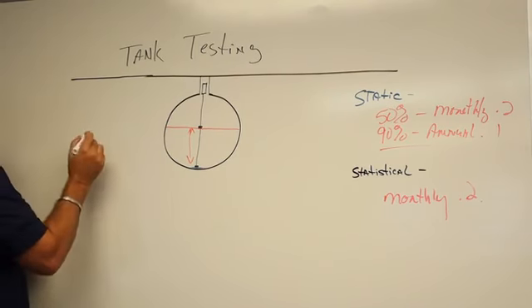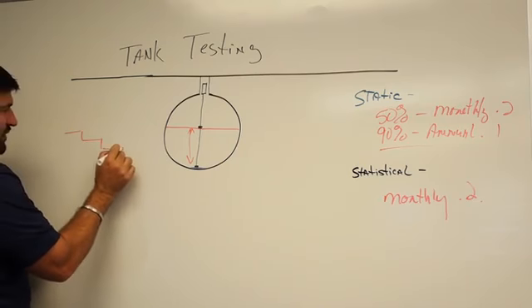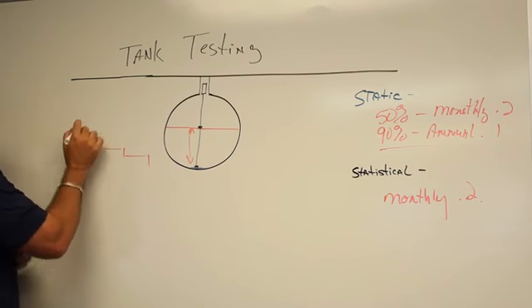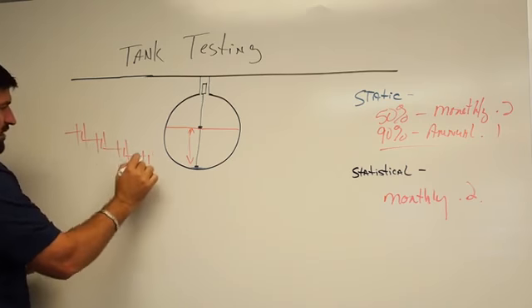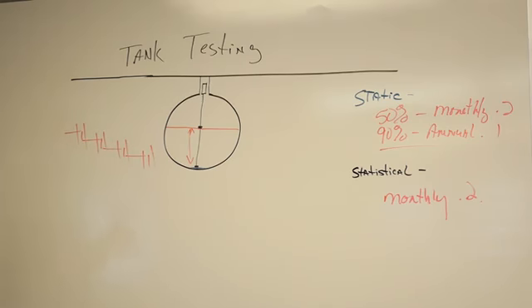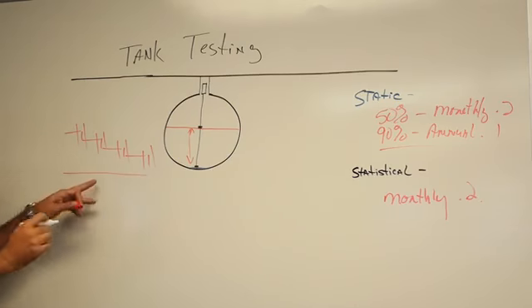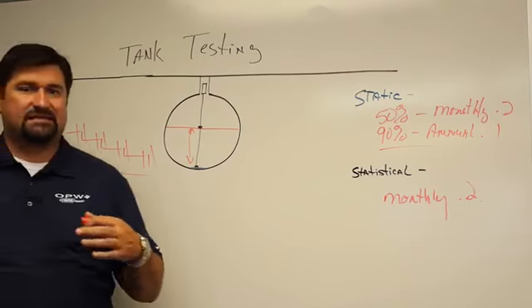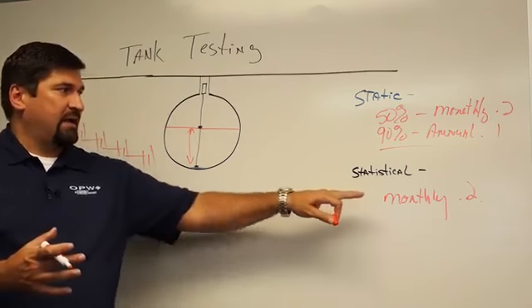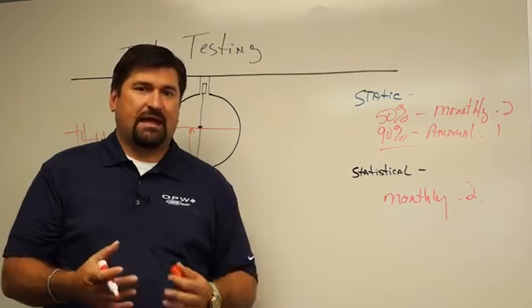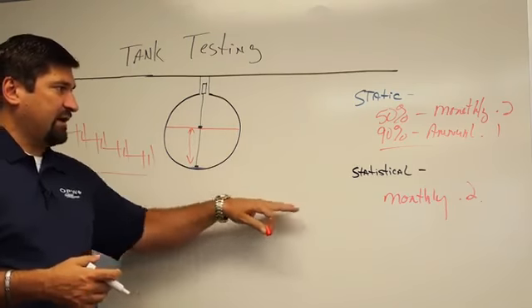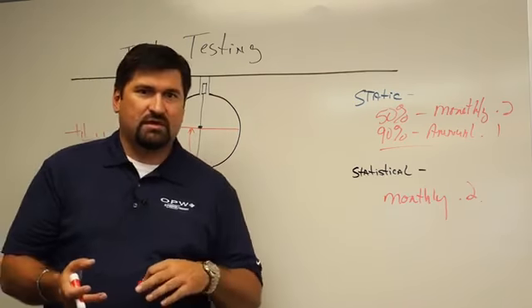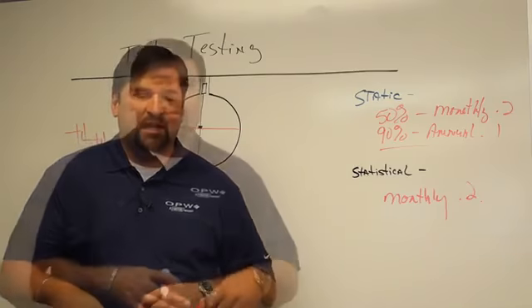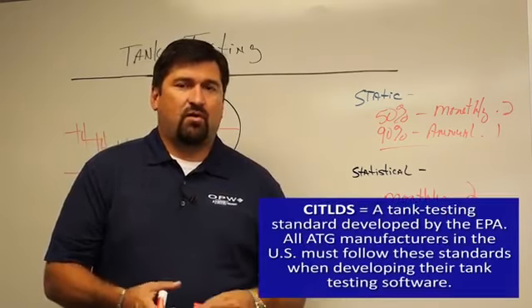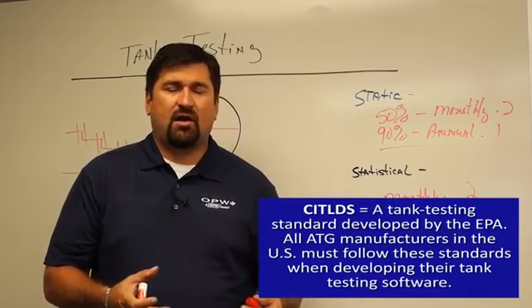So basically what I'm doing is looking at levels within the tank, and I'm knocking off the points that were dispensing cycles, and I'm taking all of my lines and adding them together to see if I can create what is a basic static test, just to create my monthly 0.2 to make sure that the tank is not leaking. Now when I start talking about statistical tests, you'll hear words like CSLD, SLD, SCALD. We're all based off of the CITLDS protocol. So when you look at it, we're basically all the exact same.